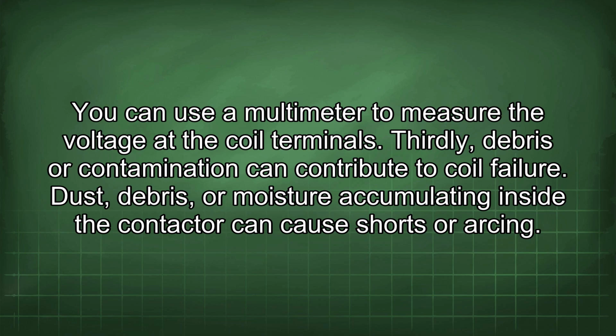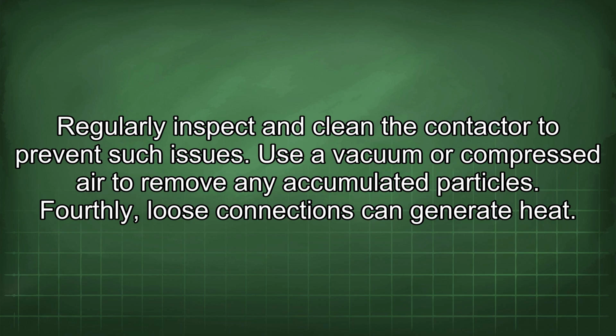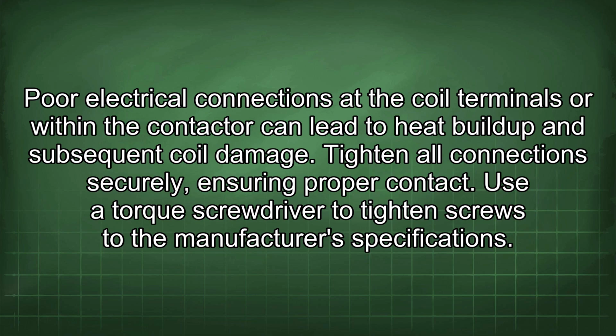Thirdly, debris or contamination can contribute to coil failure. Dust, debris, or moisture accumulating inside the contactor can cause shorts or arcing. Regularly inspect and clean the contactor to prevent such issues. Use a vacuum or compressed air to remove any accumulated particles. Fourthly, loose connections can generate heat. Poor electrical connections at the coil terminals or within the contactor can lead to heat buildup and subsequent coil damage. Tighten all connections securely, ensuring proper contact. Use a torque screwdriver to tighten screws to the manufacturer's specifications.